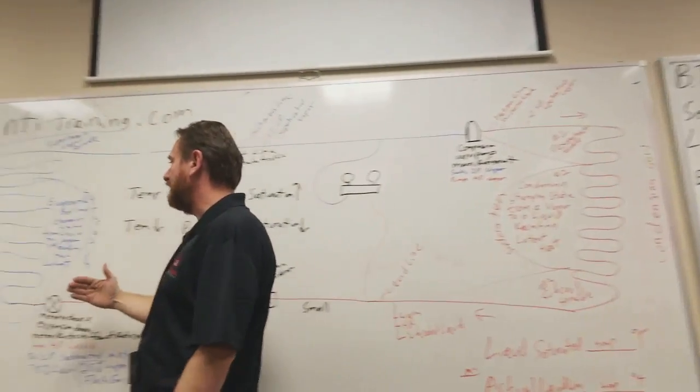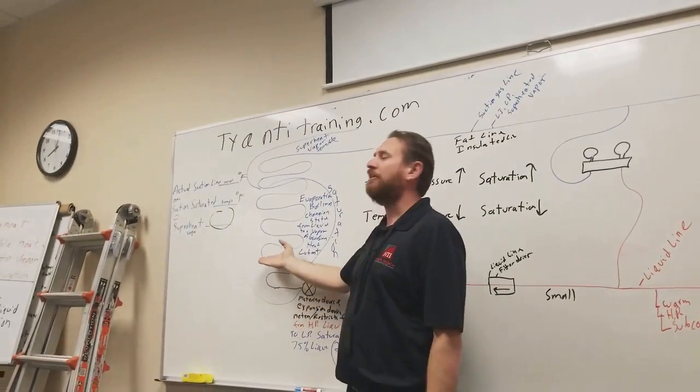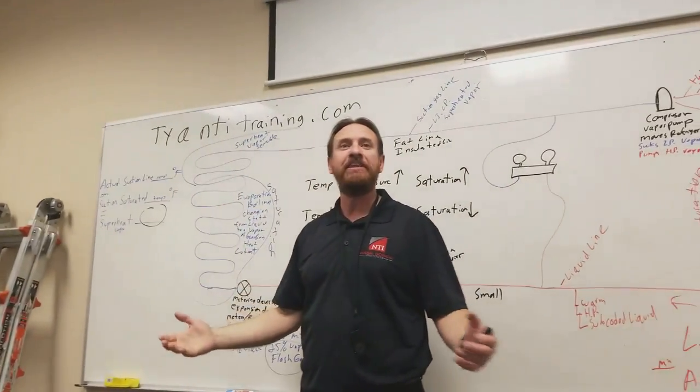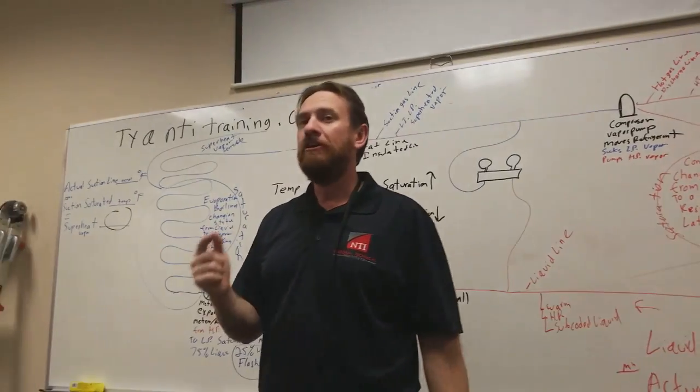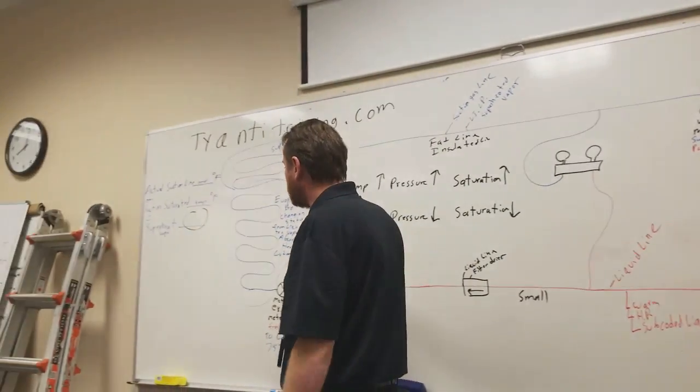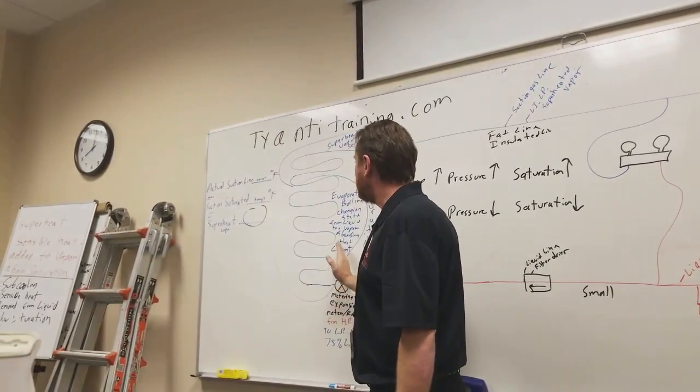That pushes more over here, causes more refrigerant to go over here, which causes pressure to go up, and now it's not freezing. And they think, oh yeah, I solved the problem. But did they solve the problem? No. Here's what happens. Now that we're getting more liquid over here, I have more liquid.